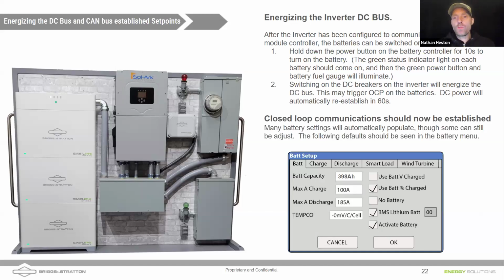And then the use battery percentage box will be checked. So the BMS will do some of the programming for you once you've enabled communications. We also want to check that activate battery box in the bottom right corner. What that'll do is if the system runs low and shuts off because of a low battery, if a DC charging source like solar comes out and is available, it'll allow that inverter to start itself up automatically and start charging those batteries. I think one of the key takeaways, Nathan, is that the battery should always be the first on during the startup and the last off if you're shutting the system down as well.